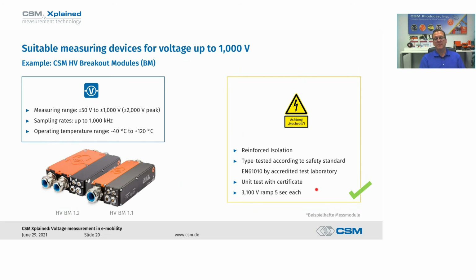Often the measurement of voltage is not just voltage, but combined with current to calculate power. There are multiple powers: instantaneous power, reactive power, etc, for doing any kind of efficiency analysis where there's power in and power out. Through evolutionary and innovative work with our customers, we have breakout modules that not only measure voltage up to 1,000 volts, but also simultaneously measure current in the same location. It's safety sealed inside the breakout modules, which are also IP67, with the same safety concept and reinforced isolation inside the module for high voltage safety.